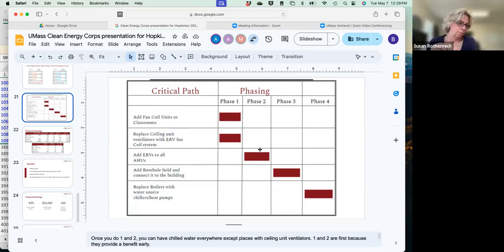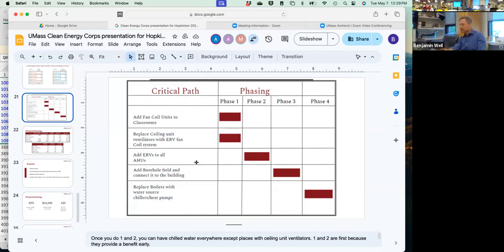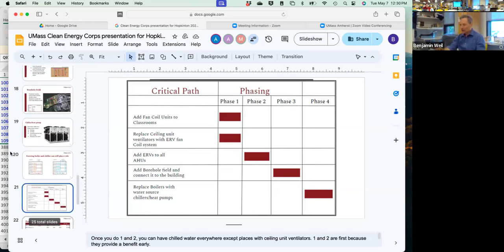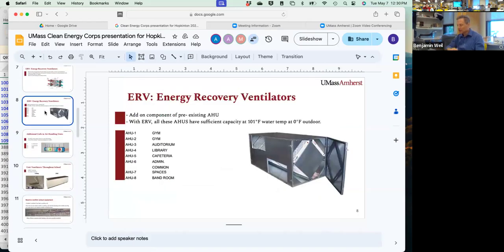Yep. The next one really is, and again, could be in your current capital plan, to look at those air handling units and decide, do I think they're going to last another 20 years or so? And if you think, yeah, they're actually in good shape, there's nothing wrong with them, I could replace a motor here and a drive there, then we're talking about the design that Anthony was talking about, which is this one from RenewAire, and it's called Applied. It's just an applied ERV, and it connects to essentially the mixed air section of your air handling unit. It doesn't have any electrical connections, it's just duct connections. The existing fans do all the work.